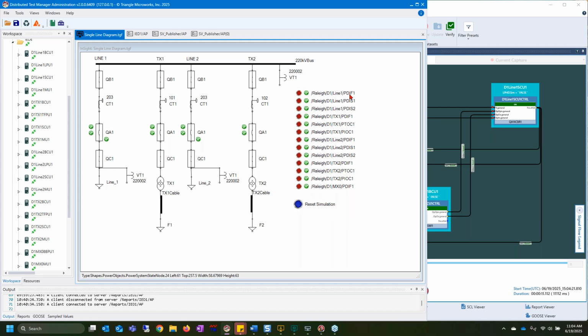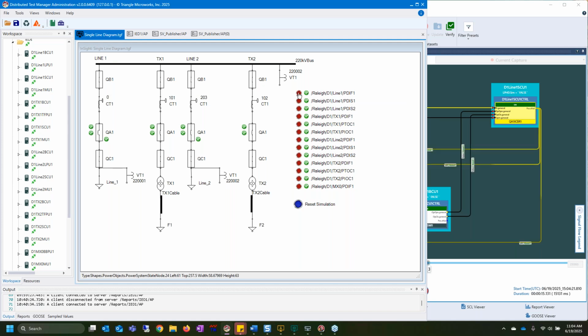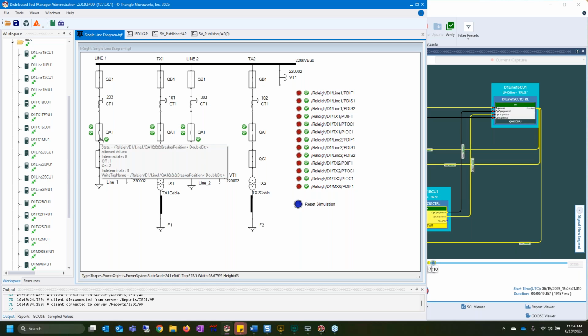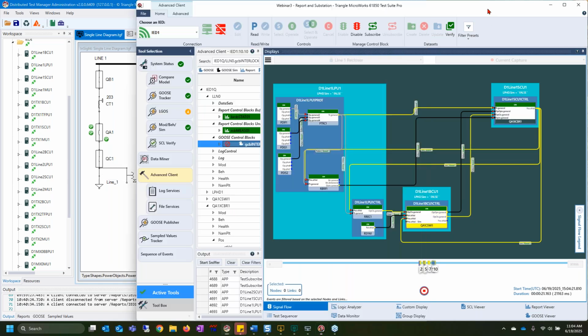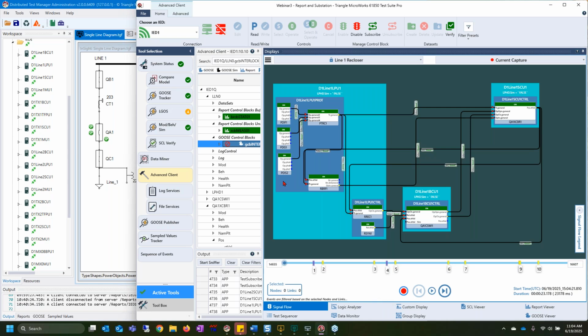I'm going to cause a differential fault on line 1. So I'll just simply click this red button here. The breaker will open, the breaker will close due to a reclosing function, and I will go back to Test Suite Pro and stop the recording here. So we can see a timeline has now been generated at the bottom, and this timeline will walk you through all of the communications that happened during that differential fault. So I will go ahead and click the next button.